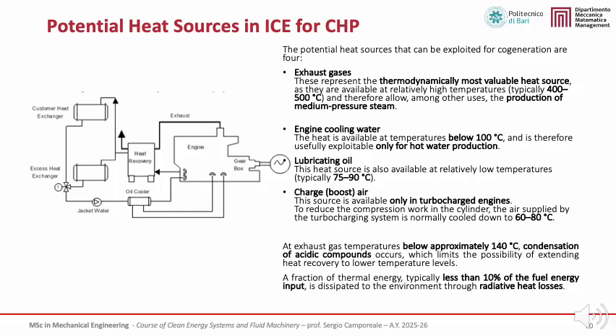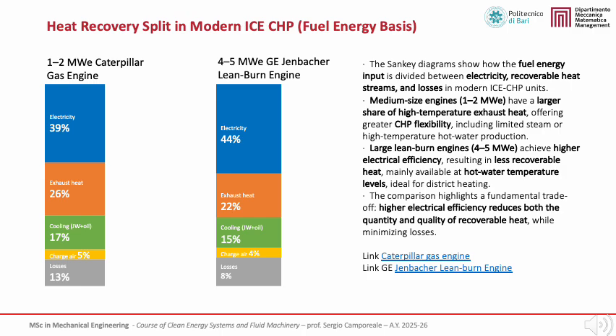Finally, a fraction of the thermal energy, typically less than 10% of the fuel energy input, is unavoidably dissipated to the environment through radiative heat losses. This slide illustrates how the fuel energy input is divided between electricity, recoverable heat streams, and losses in modern internal combustion engine CHP units. The comparison is based on Sankey diagrams for two representative engine sizes. On the left, we consider a 1 to 2 megawatt electric gas engine, representative of medium-sized CHP units.